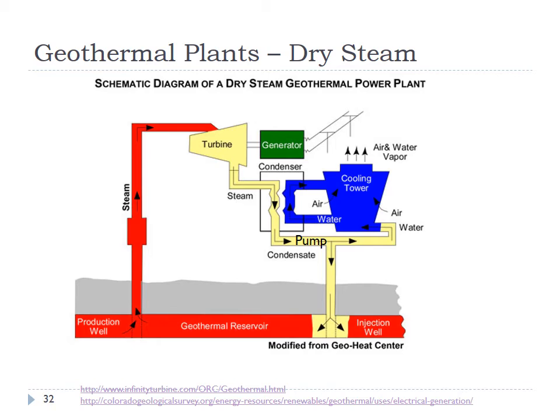So to create the liquid from the vapor, you need a cooling tower. Then you need a pump to bring that liquid back up to at least atmospheric pressure, and send that to the injection well. Some of that liquid goes to your cooling tower and evaporates, which is why it's often easy to see geothermal power plants - you have massive amounts of water vapor leaving cooling towers, turning into water droplets, which is what you see.